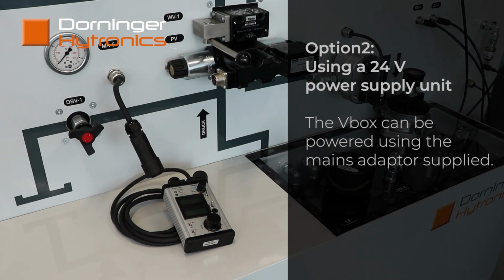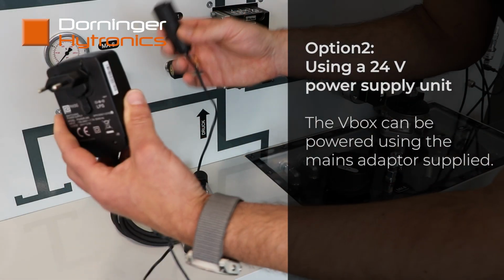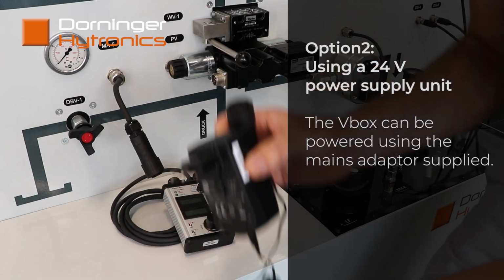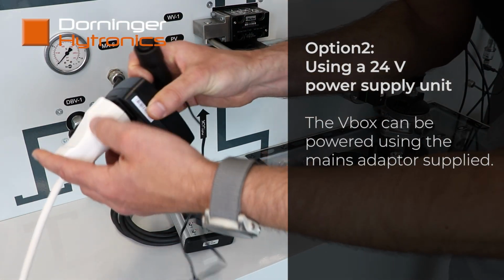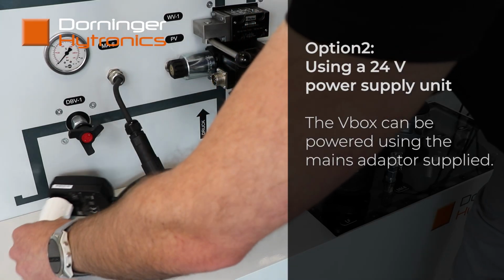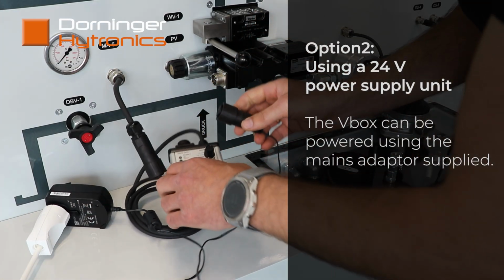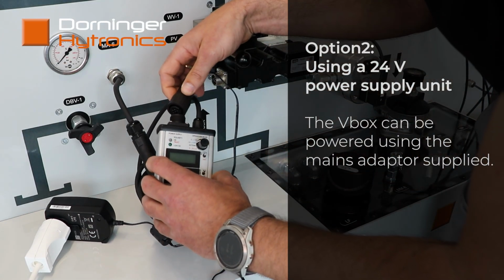Option 2. Power is supplied by an external power supply unit connected to a 230-volt main socket. We connect the Vbox to supply it with power. As always, we check the indicator lights to verify the polarity before connecting the Vbox to the valve.